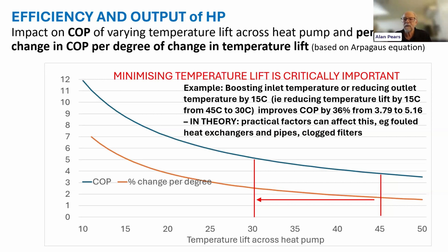These are real opportunities. A lot of people think that if you reduce the temperature difference by a degree, that achieves a couple of percent savings. But when you look at the thermodynamics, once you get down to smaller temperature differences, you actually get a bigger improvement in performance per degree reduction. It's one of these funny things.